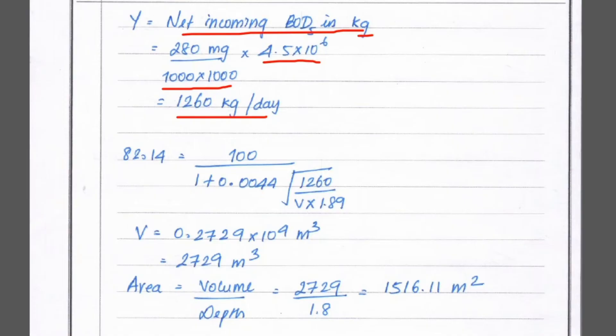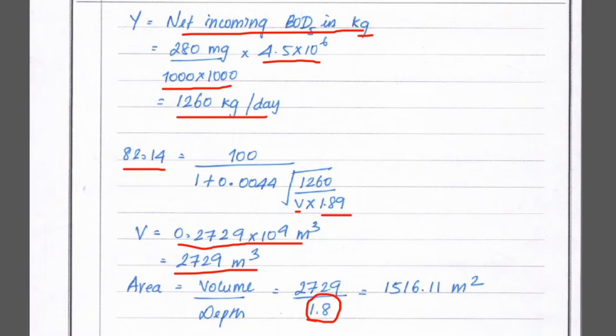Substituting all values into the formula: 82.14 = 100 / (1 + 0.0044 × √(1260 / (v × 1.89))). Solving for v, we get v = 0.2729 × 10⁴ m³ = 2729 m³. Then area = volume / depth = 2729 / 1.8 = 1516.11 m². That is the area of the trickling filter.